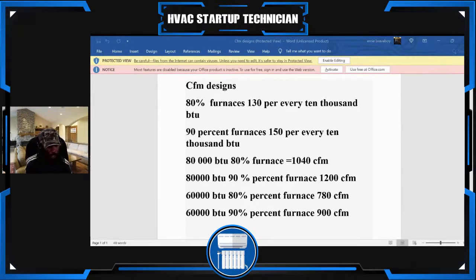So I'm going to continue now, and I'm just going to touch base and talk about 90% furnaces, because with 90% furnaces, the numbers are a little bit different. So remember I said in the 80% furnaces, we're doing 130, but now with 90%, we're doing 150 per every 10,000 BTUs. So 150 times every 10,000 BTUs. The math is simple. The math is the same. So you're going to do that 150. Now you're doing 150 times 8 if it's 80,000 BTUs. You're doing 150 times 6 if it's 60,000 BTUs. And if it's a 70, you guys kind of get the picture.